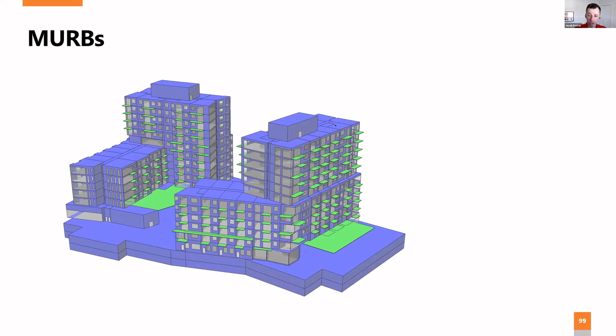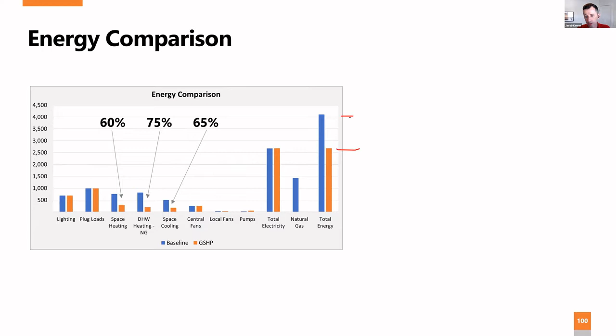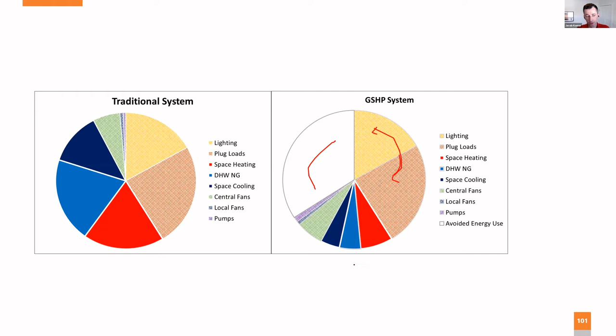Just by adding geo, doing no other upgrades, we reduced the space heating by 60%, space cooling by 65%, and hot water by 75%. Overall, when you account for the plug loads, it's a 35% energy reduction. Your biggest energy portion now is lighting and plug loads. Your heating and cooling are now a small portion. And the interesting thing is this building is cooling dominant because of the large windows, the south and west exposures, and a sunny climate. It's very cooling dominant.